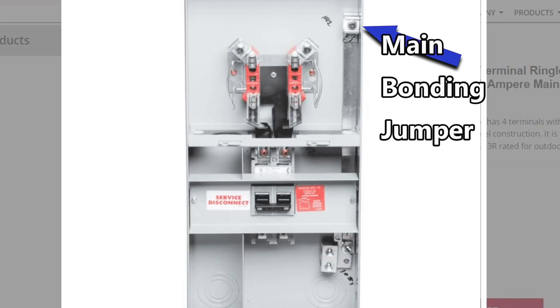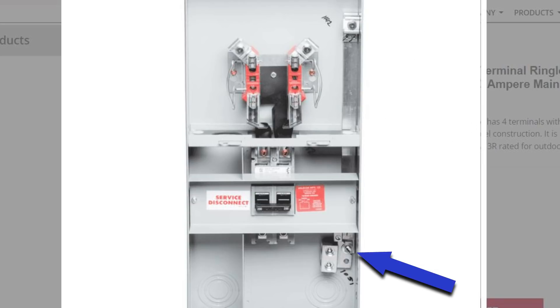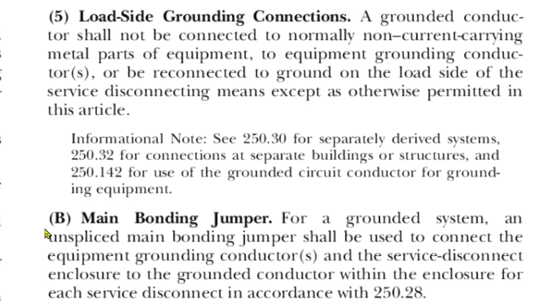Here we are at NEC 2020 250.24 B, main bonding jumper for a grounded system. An unspliced main bonding jumper shall be used to connect the equipment grounding conductor or conductors and the service disconnect enclosure to the grounded conductor within the enclosure for each service disconnect in accordance with 250.28.